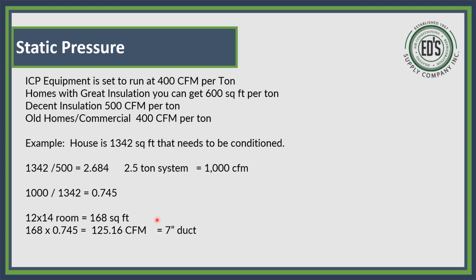That's going to be my 7-inch ductwork. Now, you need to look at ASHRAE's ductwork sizes because flex will carry less than what hard pipe does. But if I'm hard piping my duct, I will be able to get 125 CFMs to that room, provided I use a 4x12 grill, because a 4x10 won't let enough in there. And I may have to go bigger than a 4x12. I may have to put a 4x14 in there just to be able to get 125 CFMs to it.